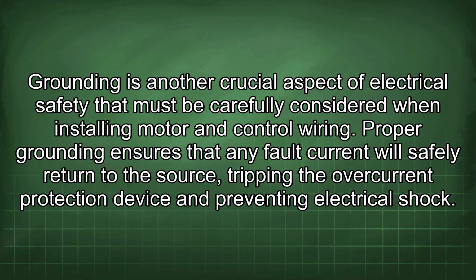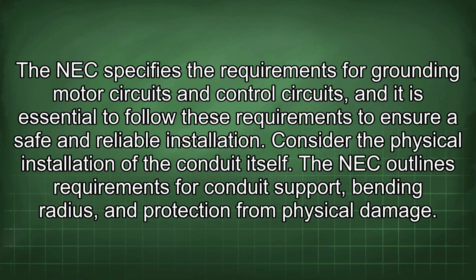Grounding is another crucial aspect of electrical safety that must be carefully considered when installing motor and control wiring. Proper grounding ensures that any fault current will safely return to the source, tripping the overcurrent protection device and preventing electrical shock. The NEC specifies the requirements for grounding motor circuits and control circuits, and it is essential to follow these requirements to ensure a safe and reliable installation.